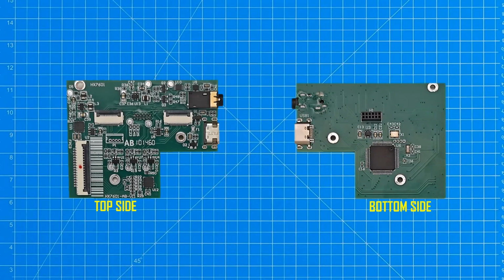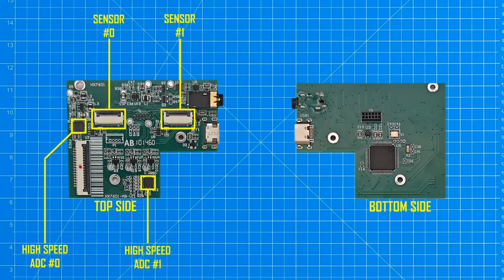The analog board itself is a fairly complex component. Although only one scintillation detector is fitted to the product, all of the circuitry required for both has been fully fitted. Both connectors for the detector modules are present, as are their respective high-speed analog to digital converters.